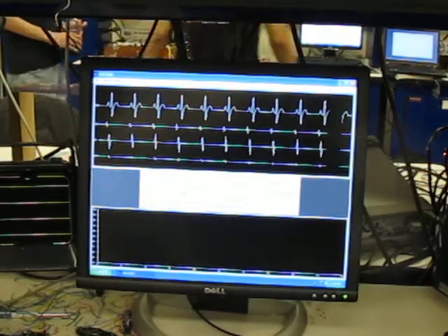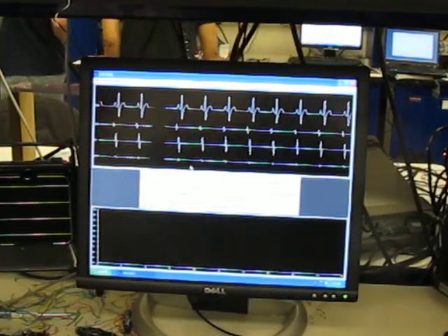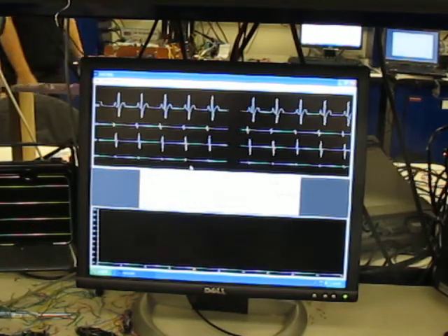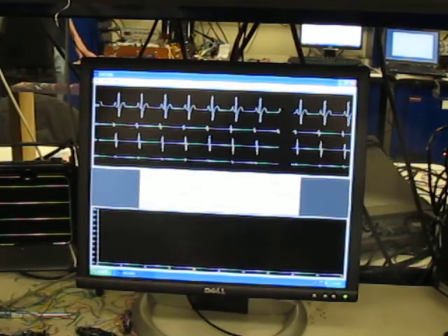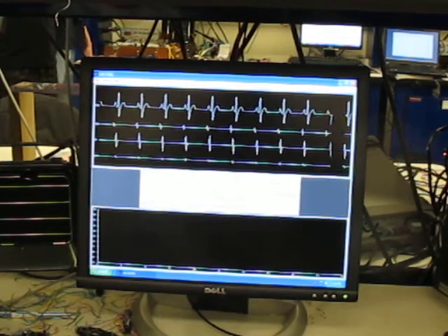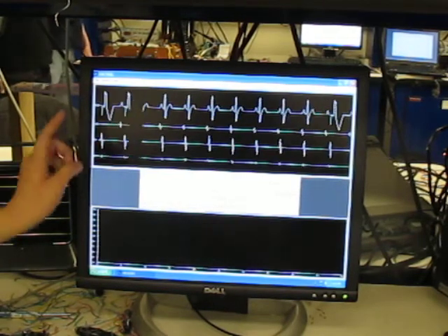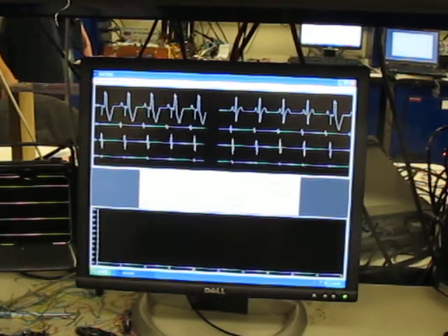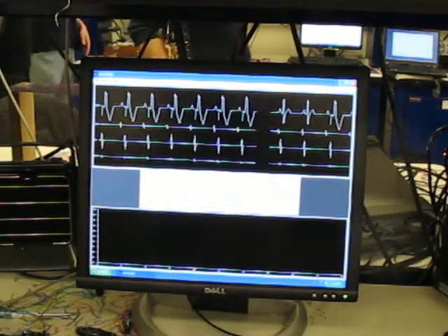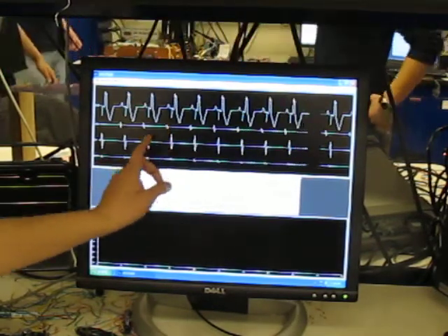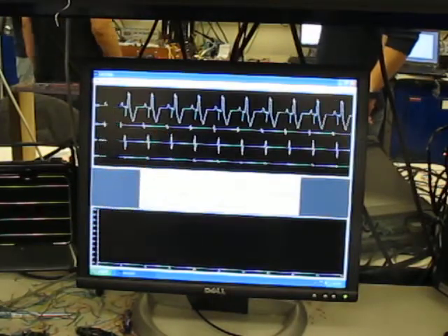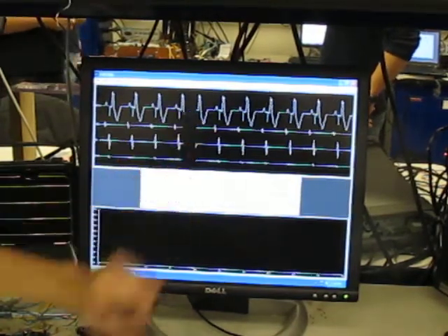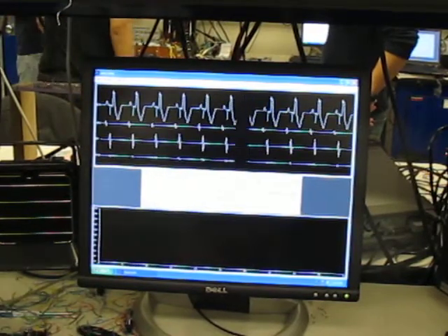Now, if I suddenly block, so right now it's in something called normal conduction, which means the two chambers are communicating. If they're not, and we're in complete heart block, then my pacemaker should take over the ventricle. And so we see pacing only in the second portion. And how do you detect the pacing? It's a threshold. No, no, but I mean, how do you know it's being paced right now? Not everybody who's watching this video knows how this works. The little blue bars are pacing. And so that's me pacing.